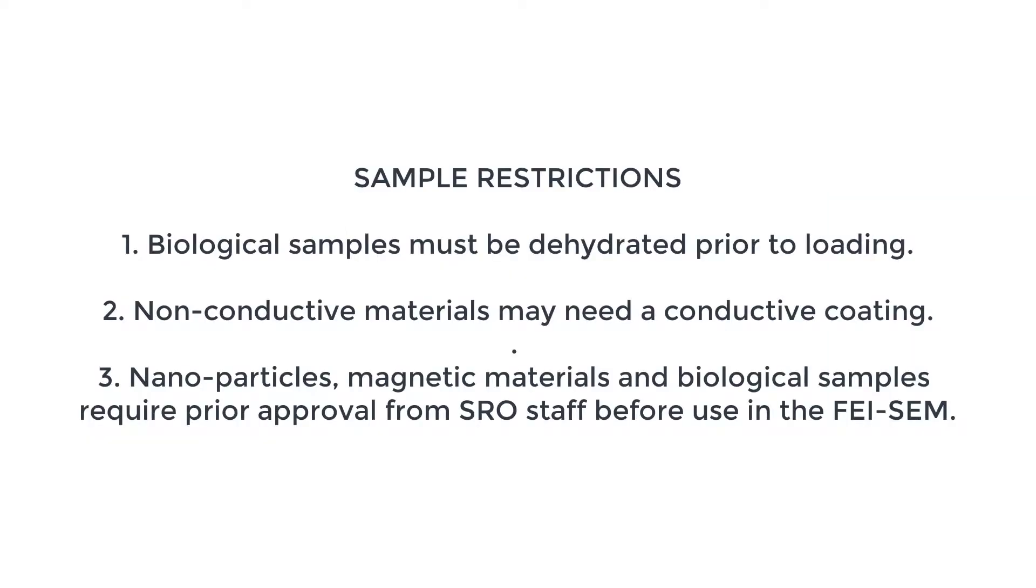Before we begin, there are several sample restrictions you need to be aware of. First, biological samples must be dehydrated prior to loading. Next, non-conductive materials may need a conductive coating. And finally, nanoparticles, magnetic materials, and biological samples require prior approval from SRO staff before use in the FEI SEM.